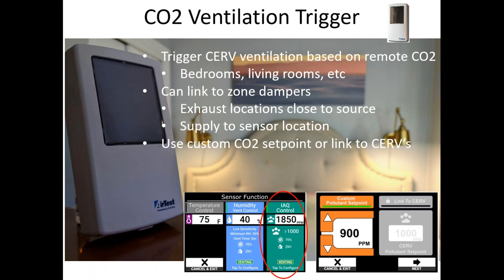You can link this to zone dampers too. On the exhaust side, you may have dampers closed down in regions further away from the source of the CO2. And then if you had supply dampers, you could also direct the fresh air to that specific room. So the master bedroom, that's where this is located. You could have the fresh air mostly diverted to that specific location.